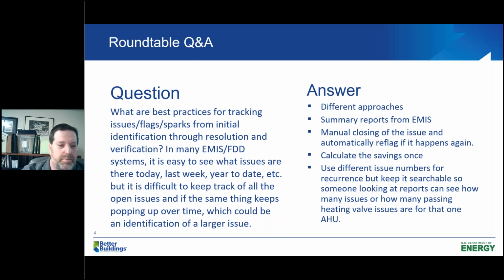Summary reporting can be very important, not just for closing out issues, but also for assigning work orders. If you find there's a specific kind of damper related issue, it may be assigned to specific in-house people to address. If it's a programming related issue, you'll assign it to the BAS vendor to go through and change the programming. Also on large campuses, sometimes different buildings are assigned to different people, so one could be assigned to one building or group of buildings while another set is assigned to someone else.